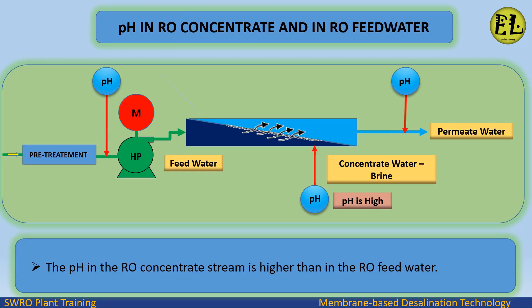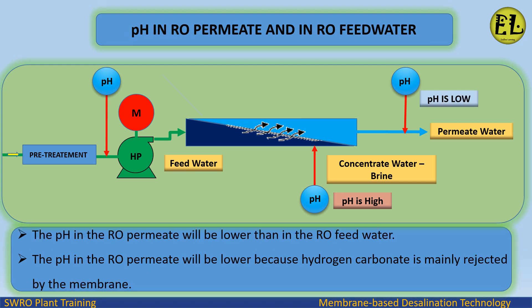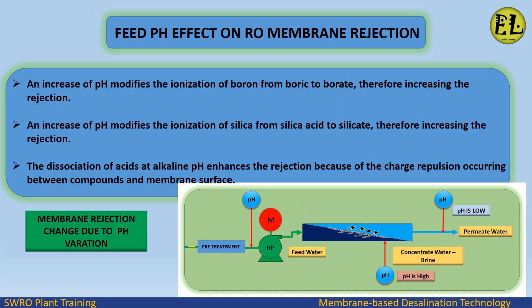pH in RO: the pH in the RO concentrate stream is higher than in the RO feed water. Regarding pH in RO permeate versus RO feed water, the pH in the RO permeate will be lower than in the RO feed water, because hydrogen carbonate is mainly rejected by the membrane.